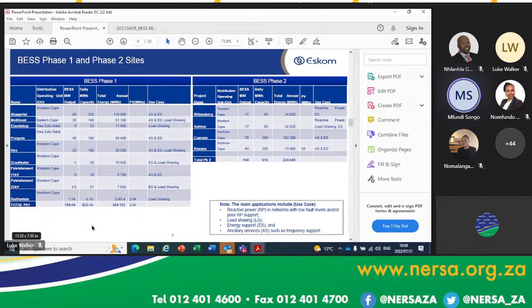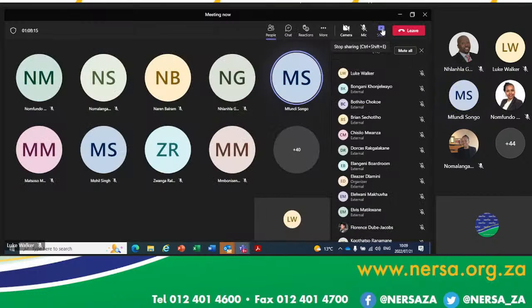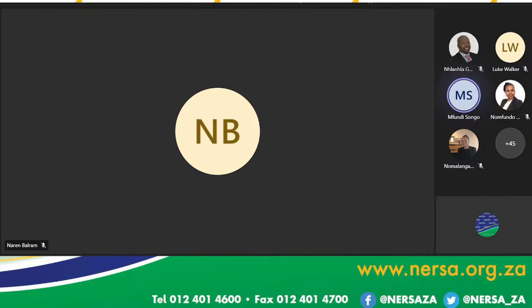The design of the choice of 4 hours was premised on the fact that peak loading starts at around 5 p.m. and lasts up to around 9 p.m. So the specification sent to the market required a minimum of 4 hours of battery availability. In those 4 hours, regarding congestion, if all 200 megawatts is available, charged during the day, and at 5 or 6 p.m. we need one unit of say 600 megawatts, switching on the 200 megawatt BESS for 4 hours means you avoid having to switch on that unit. You won't feel the absence of that unit in the system. That is how it is being perceived.